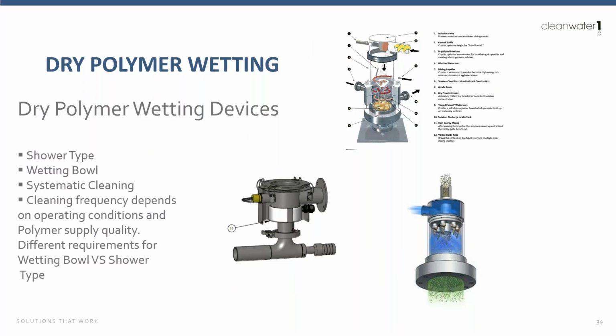So one of the things that we also want to look for in here is, do we have a level sensor or an overflow sensor in that wetting bowl? As far as design considerations, it's important to look for wetting bowl systems that have the added features such as that plunger to close off the volumetric feeder discharge, as well as that mechanical impeller to induce high mixing energy to more properly and effectively wet that polymer as it goes to the tank.